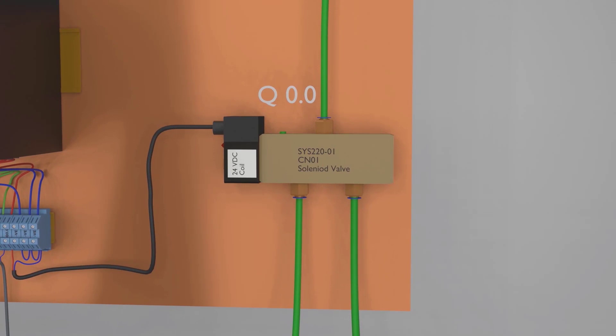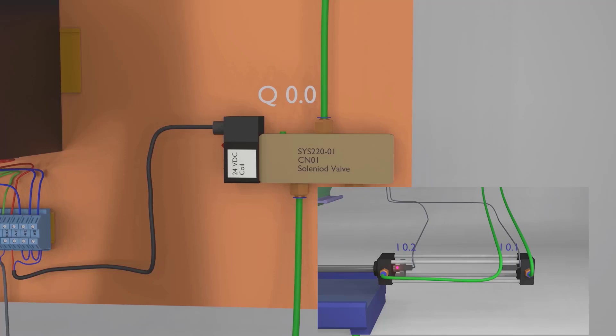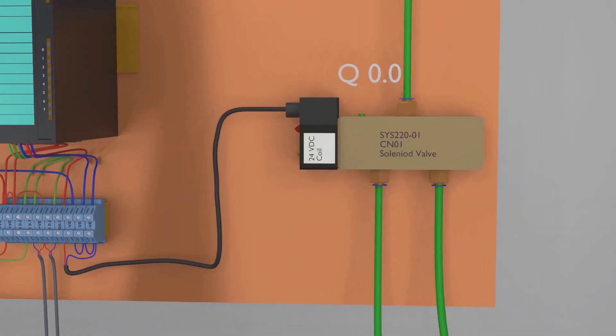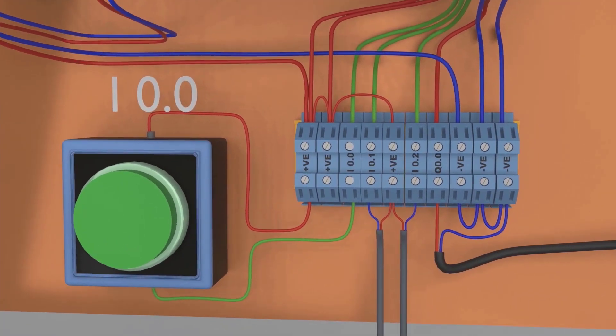The cylinder is pneumatically controlled by a 5/2 way solenoid valve, whose coil is connected at output Q0.0 of the PLC. Whenever Q0.0 is turned on, the cylinder moves forward. Whenever Q0.0 is turned off, the solenoid valve coil is deactivated and the cylinder moves in the backward direction. We also have a push button connected at input I0.0 to start the process.